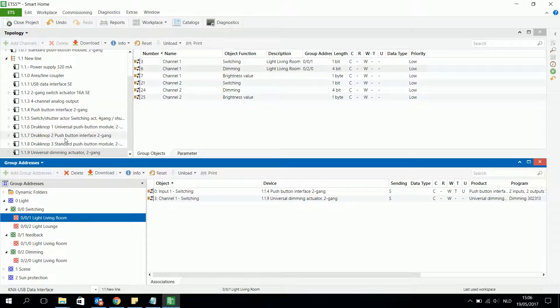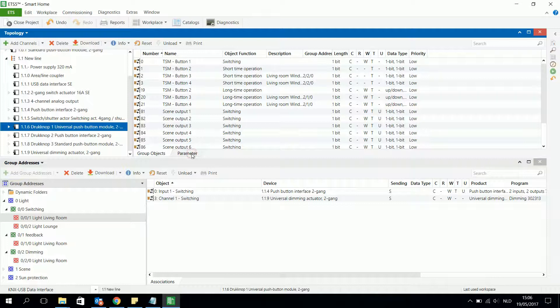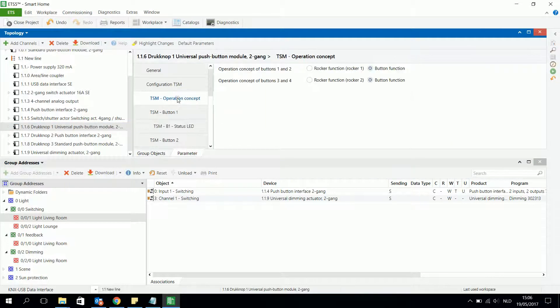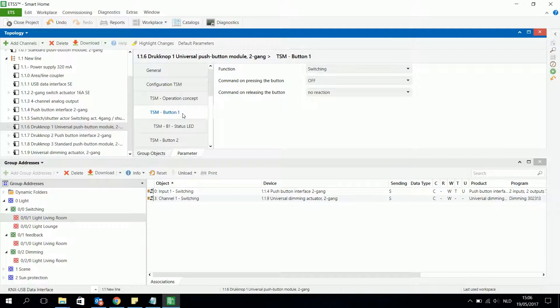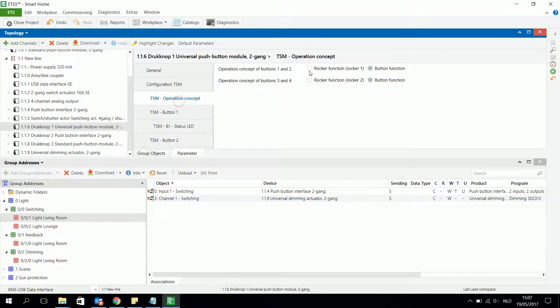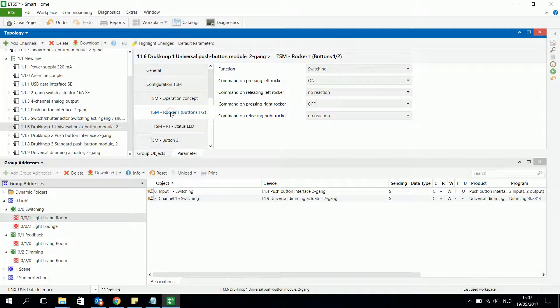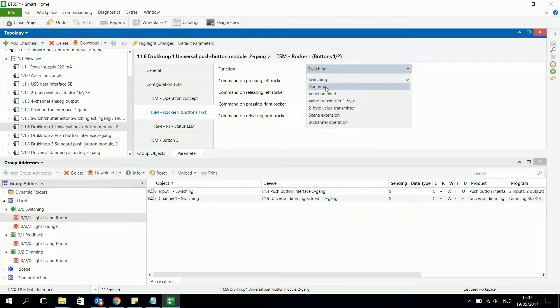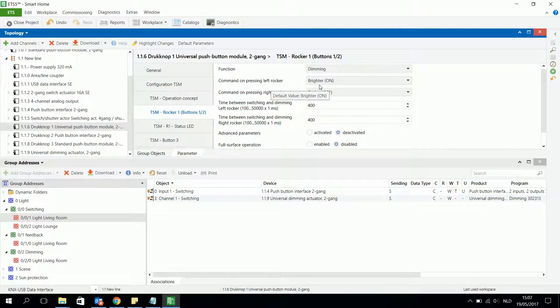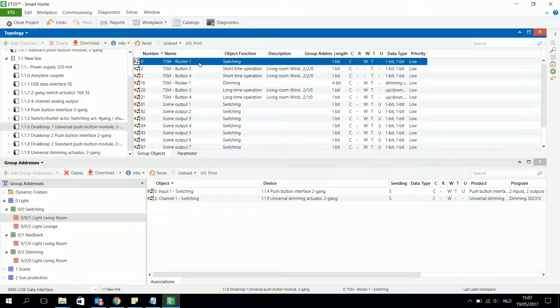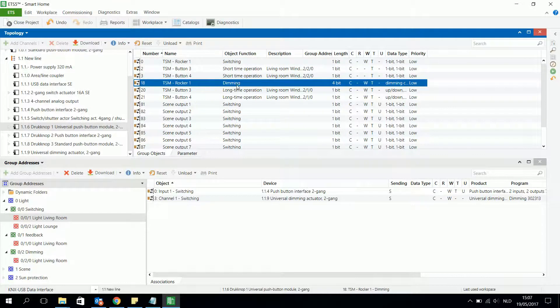I can also use another pushbutton, for example 1.1.6. Instead of programming buttons 1 and 2 separately, I can choose the rocker function — two buttons that work together. The left button can be on and brighter, the right can be darker and off. Looking at the objects list, rocker 1 has both a switching object and a dimming object.